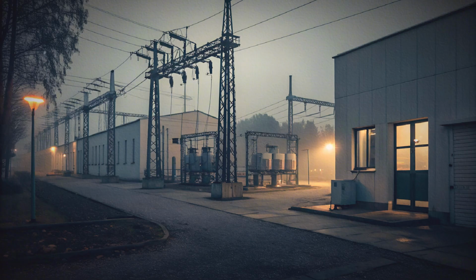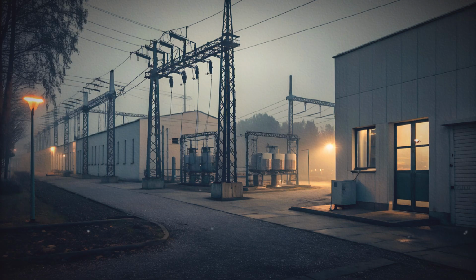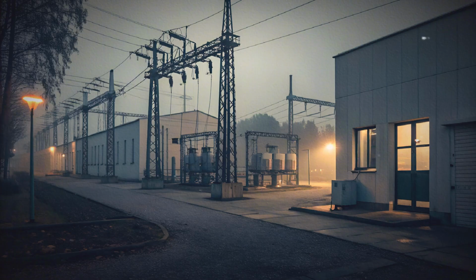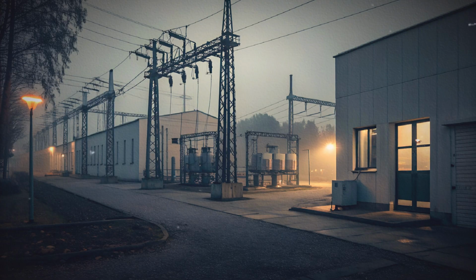Maintenance and testing are regular activities. Breaker timing tests, oil sampling and analysis, thermal imaging and relay testing reveal degradation before failure occurs. Scheduled maintenance minimizes the risk of unexpected outages. Components such as transformer bushings and insulators are inspected for mechanical and electrical integrity. Maintenance uses established procedures that include isolation, grounding, and verification steps to ensure safe work conditions for personnel.